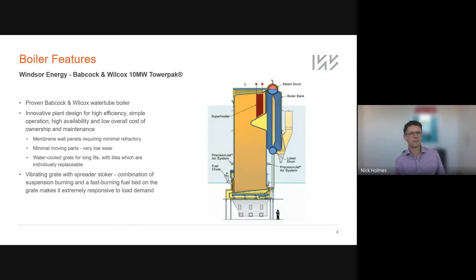One of the other features of this style of grate is it's called a spreader stoker, so the fuel is spread onto the grate. A lot of it burns in suspension, so it's a fast reacting boiler. So if you've got a load swing or a load profile that's changing quite a lot, this boiler will follow that load swing very quickly. There's no big inertia of fuel that sits on the grate.